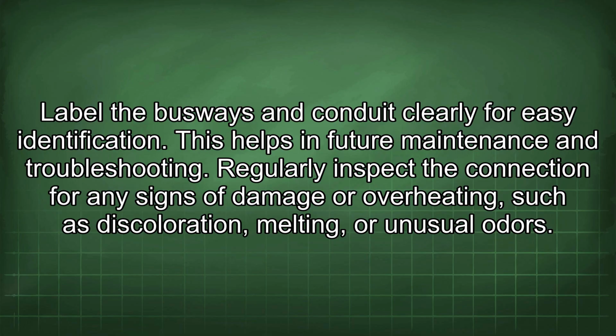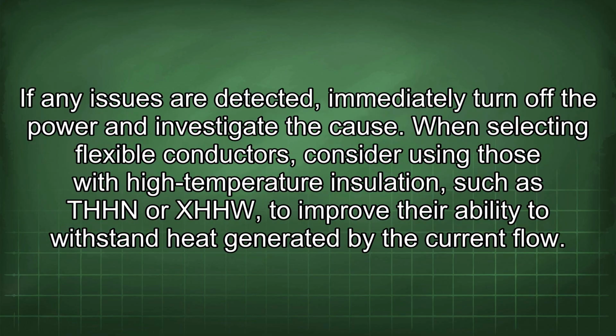Label the busways and conduit clearly for easy identification. This helps in future maintenance and troubleshooting. Regularly inspect the connection for any signs of damage or overheating, such as discoloration, melting, or unusual odors. If any issues are detected, immediately turn off the power and investigate the cause.